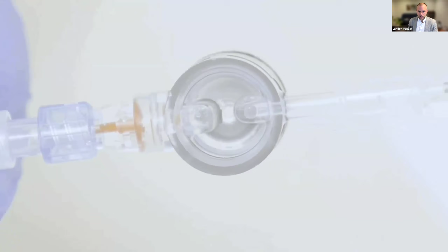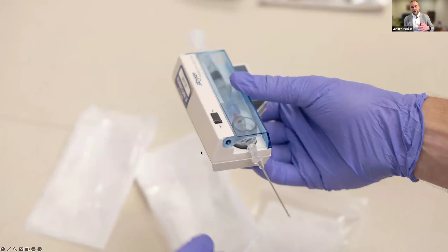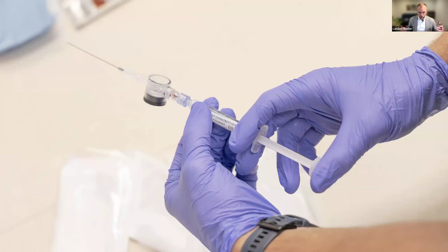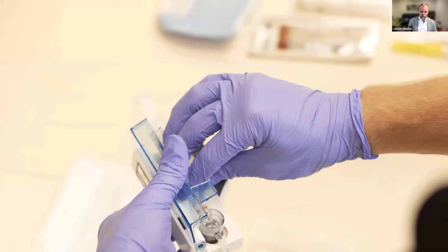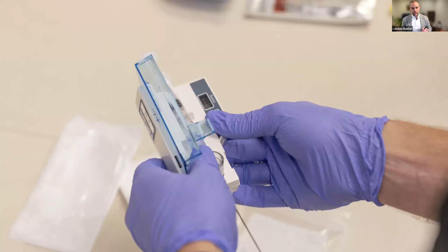So you're going to basically prime everything by making sure saline comes all the way through the needle. Then you're going to take the needle and put it into the device. Again, there are different ways, but this is the Stryker way to do it. You're going to put the device in, and you're going to click it in. That is essentially where the device is measuring the pressure, through that little chamber stem. Once you have that, it's going to click everything on and you're going to turn on the device. And that's everything to prep everything. Then I'm going to get the patient ready.